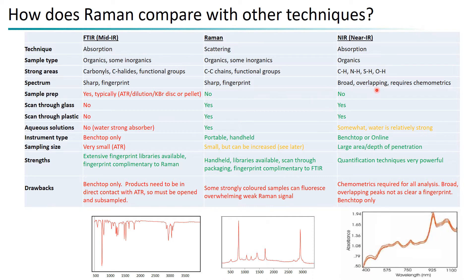Near-infrared uses broad overlapping bands and typically requires chemometrics — applying mathematical treatments to accentuate differences between samples. In terms of strengths: FTIR is most widely used with extensive fingerprint libraries available; Raman is extremely similar in that regard, but its big strengths are portability and lack of sample preparation. Near-infrared has better quantification capabilities because it is more representative of the sample and extremely reproducible for detecting small differences.